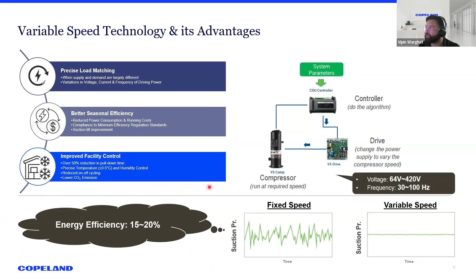Of course, with the help of the drive, the compressor can also handle various fluctuations in voltage and current, as the drive can start the compressor at a voltage as low as 64 volts, and can also start the compressor at a frequency as low as 30 hertz. This really helps not just to improve the efficiency of the overall system, but also to improve its reliability by reducing the on-off cycles, and thus improves the shelf life of the overall refrigeration system and the compressor.